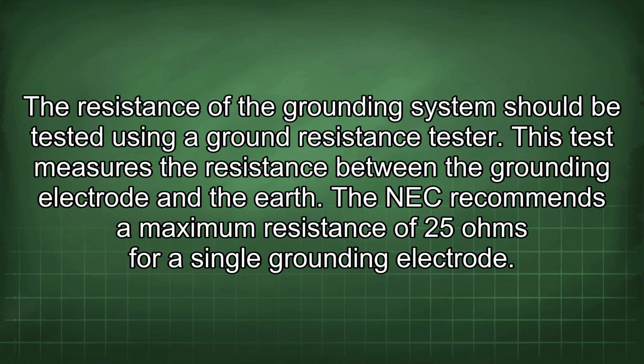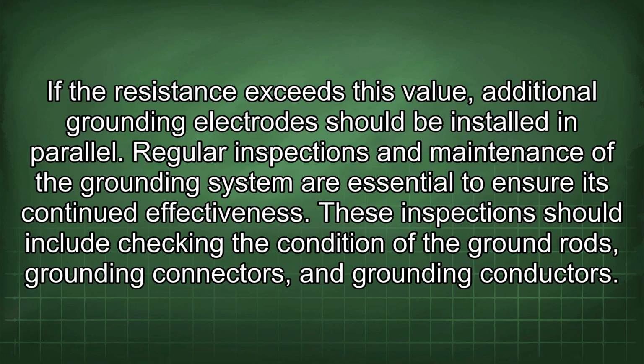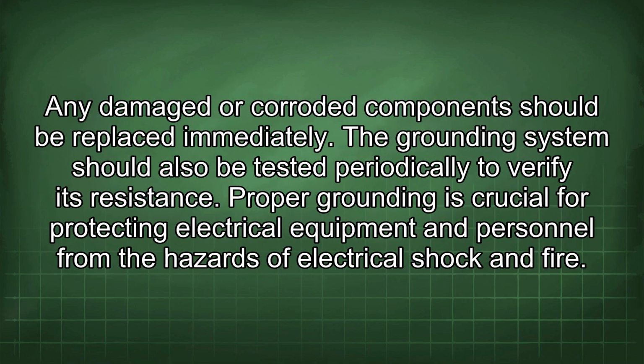The resistance of the grounding system should be tested using a ground resistance tester. This test measures the resistance between the grounding electrode and the earth. The NEC recommends a maximum resistance of 25 ohms for a single grounding electrode. If the resistance exceeds this value, additional grounding electrodes should be installed in parallel. Regular inspections and maintenance of the grounding system are essential to ensure its continued effectiveness. These inspections should include checking the condition of the ground rods, grounding connectors, and grounding conductors. Any damaged or corroded components should be replaced immediately. The grounding system should also be tested periodically to verify its resistance.